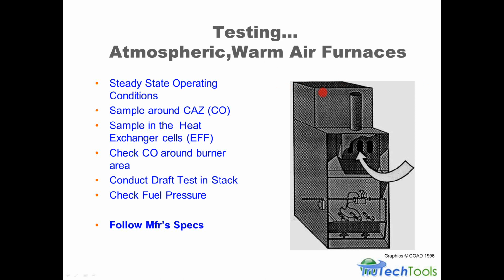When you go to test an atmospheric or warm air furnace, you want to make sure you're in the steady state operating mode. Again, warmed up, the vents warmed up, the heat exchangers warmed up, and you're running at that steady state. You do want to sample around the combustion air zone for carbon monoxide, and then do your testing in the heat exchanger cells for efficiency and for CO. And checking CO around the burner area, make sure there's no problems with that. Then conducting your draft test in the stack after dilution in the area up here, and also making sure your fuel pressure is set correctly. So these would be some of the things that a technician would follow, and again, we cover these in a little bit more detail in our under development combustion course.